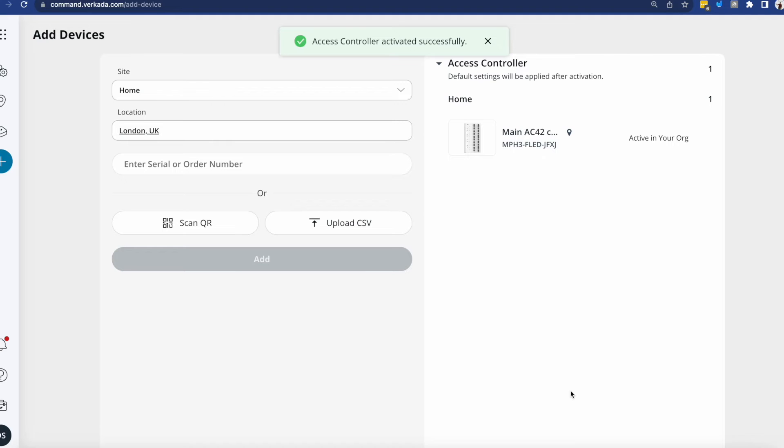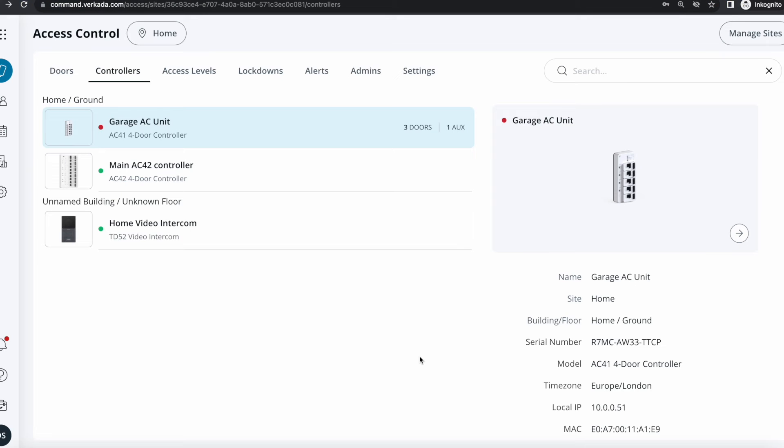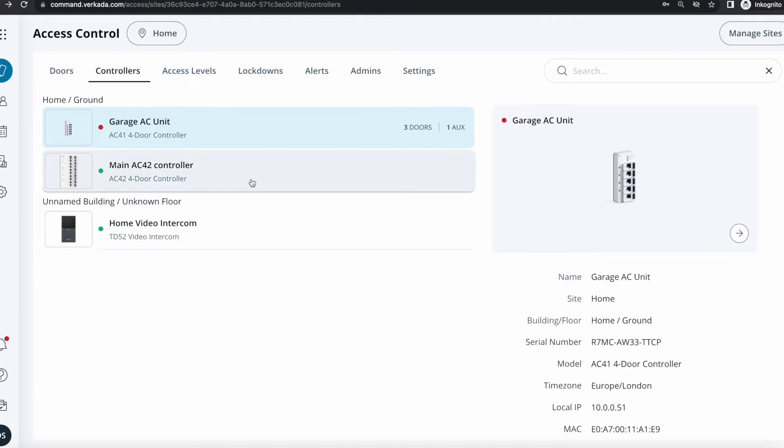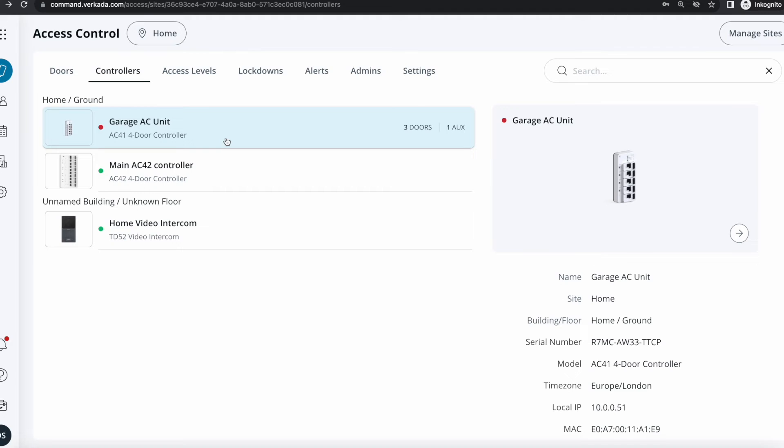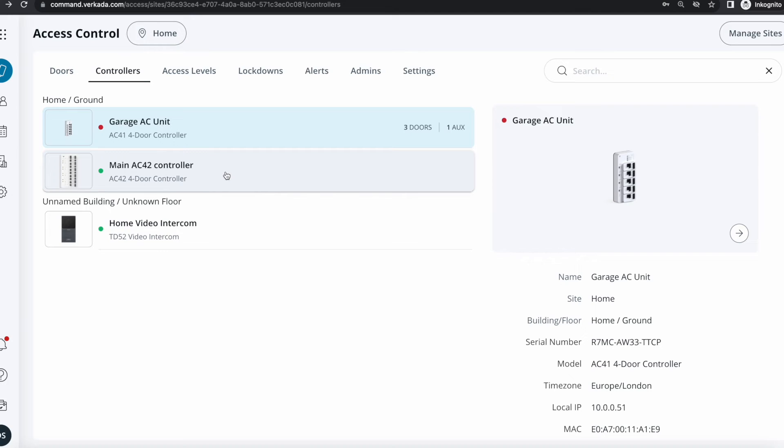The activation was successful. Just to validate that everything is up and running, I can actually see both of my controllers, the one that I swapped over and the new one. The swapped one is marked as red because it's currently offline. Command still allows me to configure it. That's a good thing about it. You don't actually need the devices up and running to start changing some of the settings. The new controller is marked as green, so everything is working as per the solid blue LED on it.